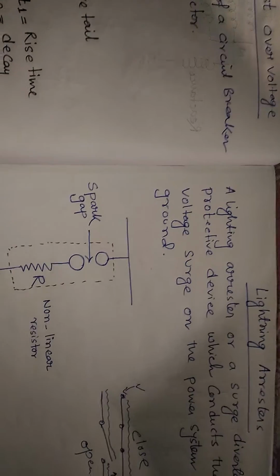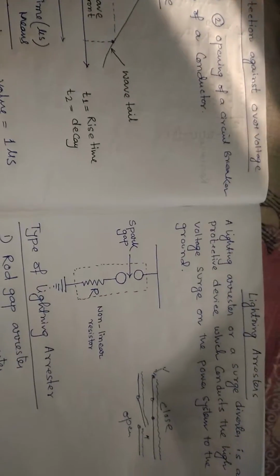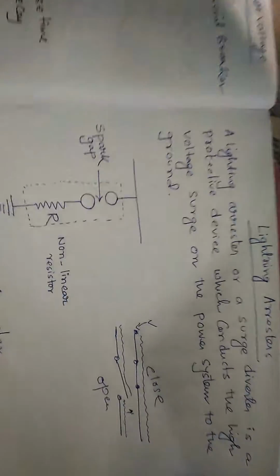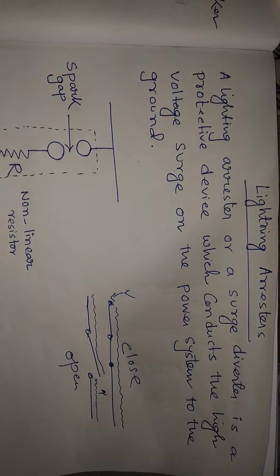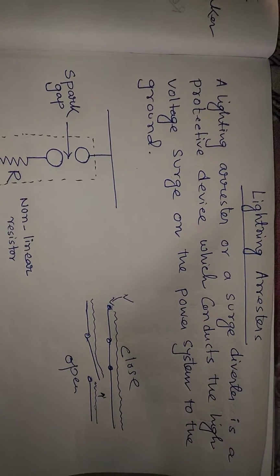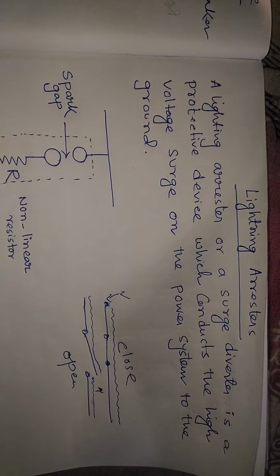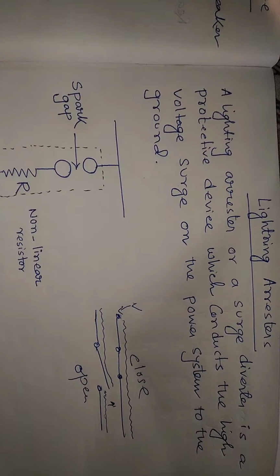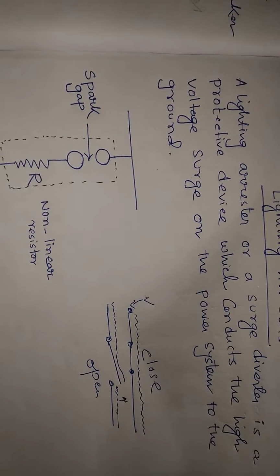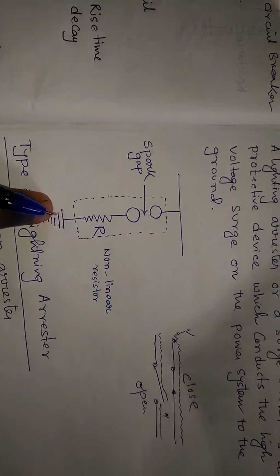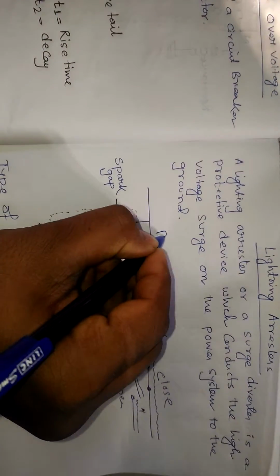And what is lightning? We have already discussed what lightning is. For protection against lightning, we use lightning arrestors in the substations or in transmission lines. What is a lightning arrestor? A lightning arrestor or a surge diverter is a protective device which conducts the high voltage surge on the power system to the ground. We draw a lightning arrestor here. This is the power line. We have to write here, this is the power line.